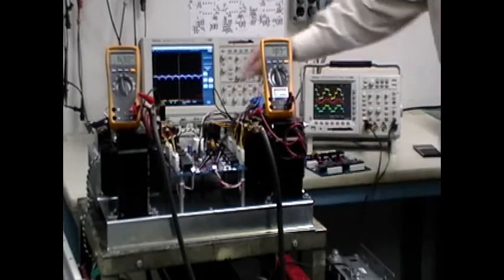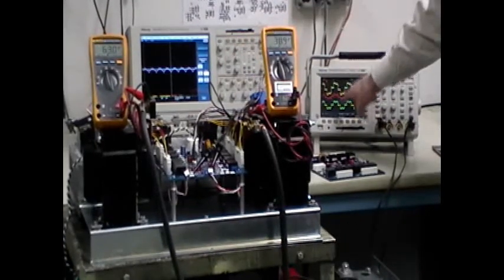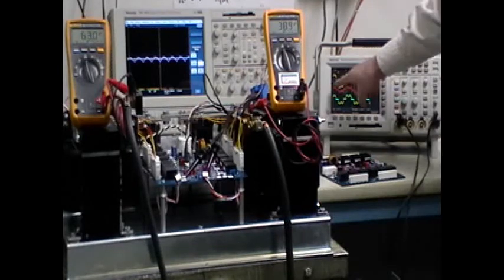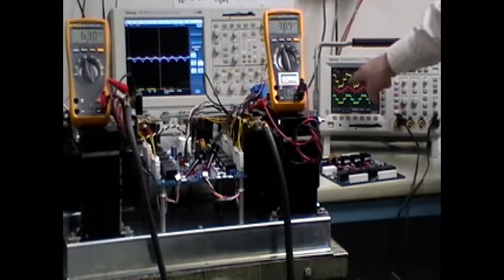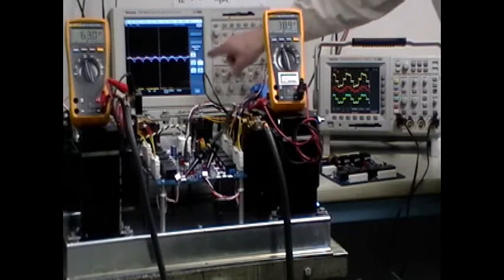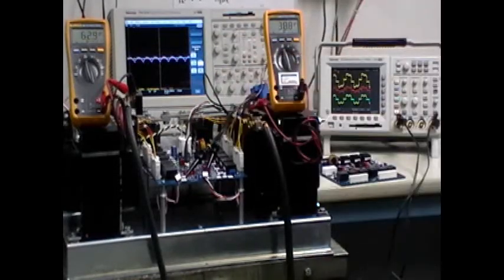We can see our secondary currents here. And you can see how the one is much higher than the other. There's actually a math function that subtracts them. And you can see there's a significant difference at 10 amps per division. This is the output voltage. And the currents will be showing as soon as we plug in our current feedbacks. So now we'll turn it off.